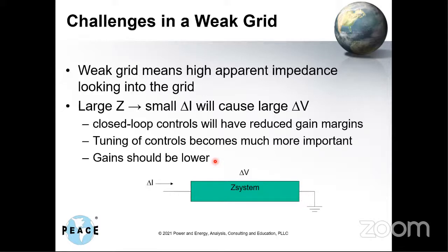So you have a lot of short circuit capability with synchronous machines. As you start to remove synchronous machines and replace them with converter-based generation, which is current limited and the current is very tightly controlled, your short circuit levels drop. You could think of that also as the effective impedance looking into the grid increasing. So you get a larger, if you will, Thevenin impedance looking into the grid from a node, like a plant. Well, if this impedance is getting larger and larger, what that means is for a small change of current injected into the grid, I'll get a large change in voltage.